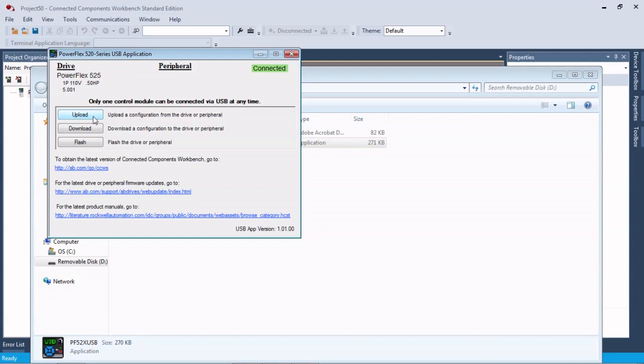From here this is where we can upload from the drive and open it up in CCW. That's where we would use that import instead of the export button. We can download to the drive or we can flash the drive first if we needed to. You can see our drive is already at 5.001 so we're fine there.